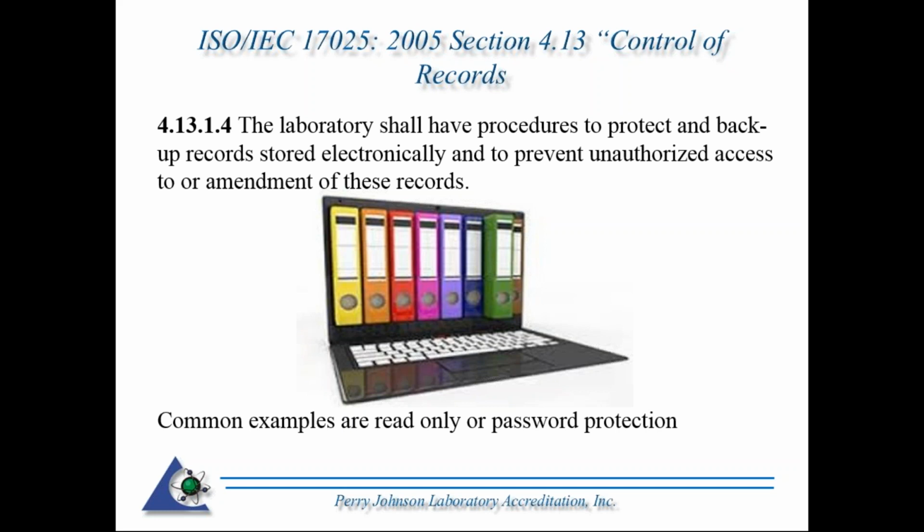Something that I would question. A technician may be actually creating records there on-site, may actually be producing a calibration report. So you should look at your off-site operations as well. They may be tied in directly to the server, but if not, you need to have a procedure in place.